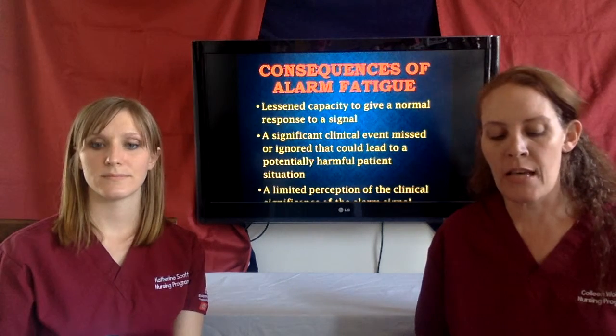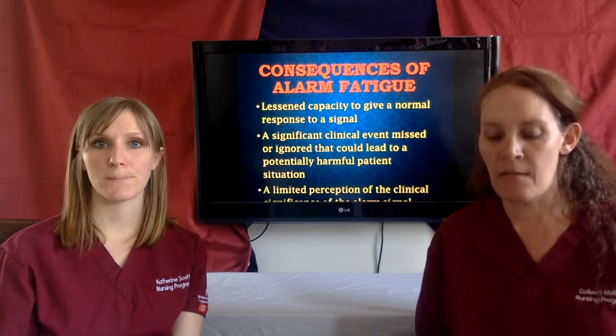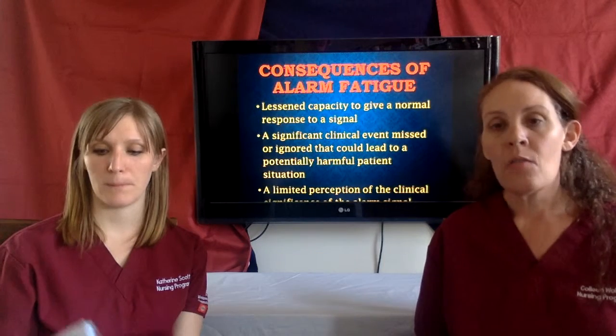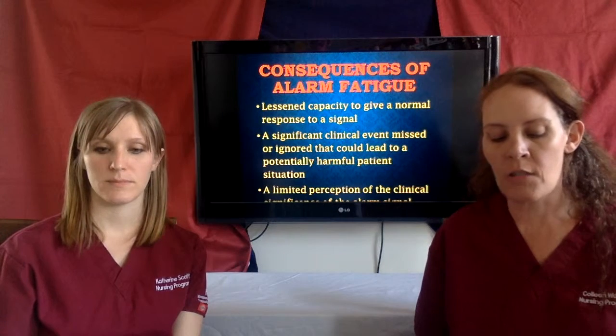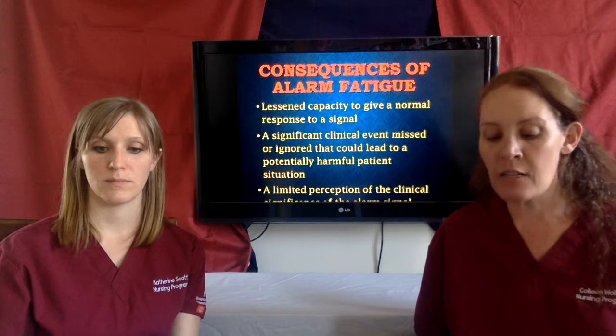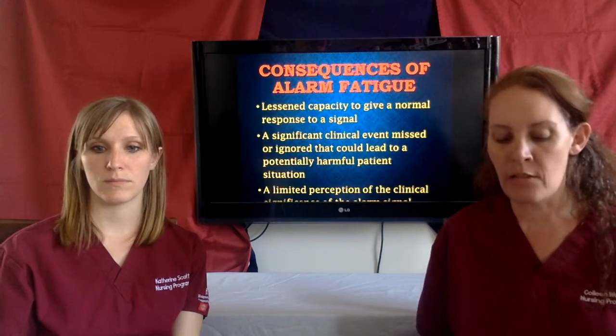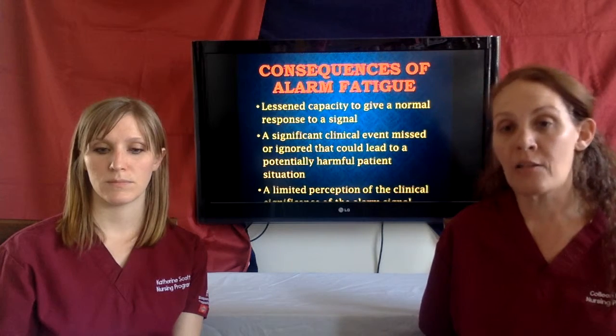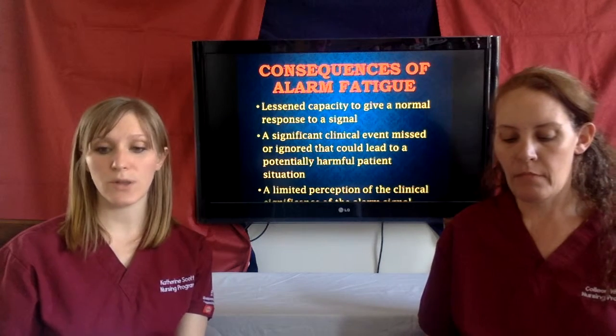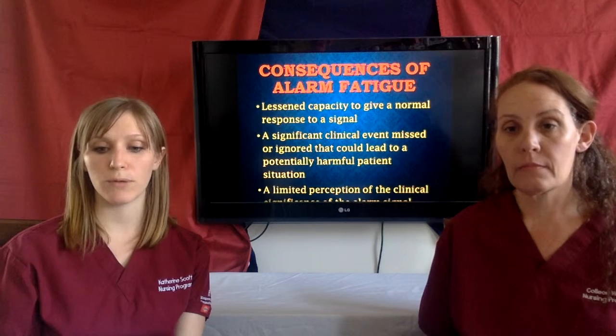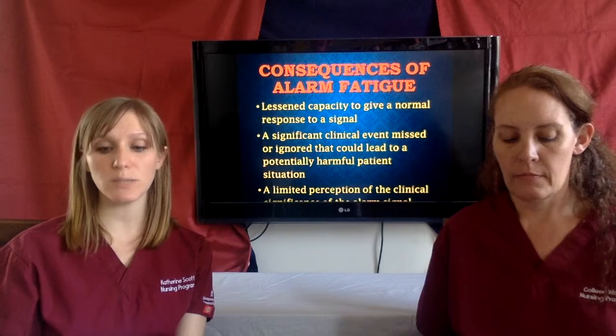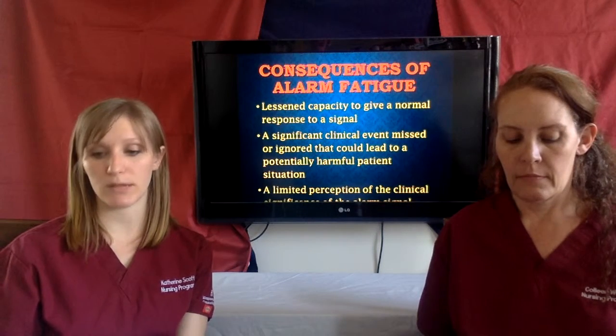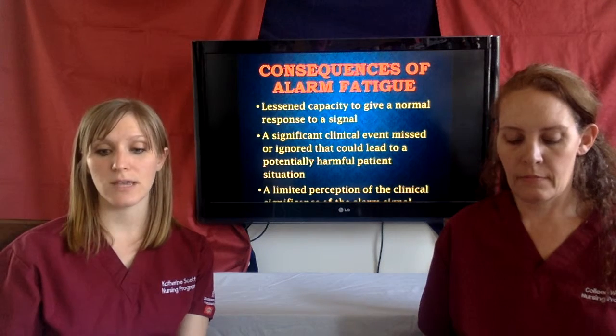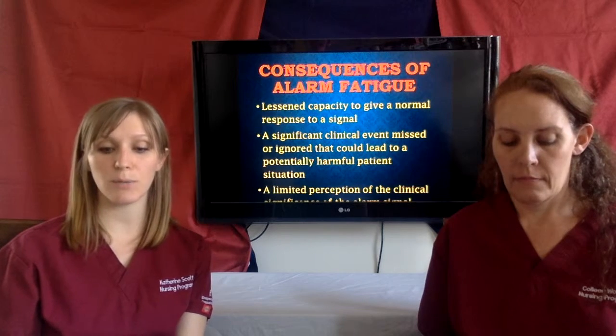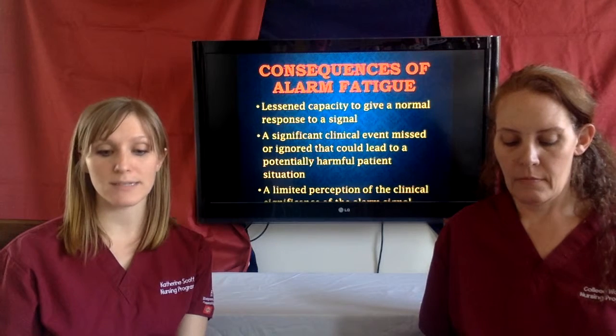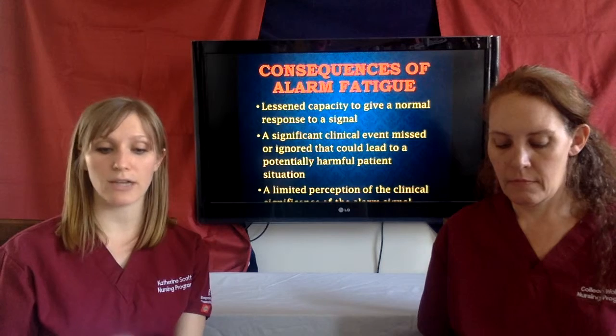Of these alarms, the Joint Commission estimates that between 85 to 99% of them do not require intervention by the nurse. We have found that evidence-based practice attributes these types of false alarms to parameter settings, not adjusting the alarms to the specific patient, improper sensor positioning, and improper skin preparation prior to the sensor application. These types of false alarms create a situation like the story of the boy who cried wolf. With so many false alarms going off, the nurse will eventually become desensitized to the alarms and not respond appropriately. This can result in missed or delayed reactions. If an alarm is false, this type of reaction isn't pertinent to patient safety. But if this alarm is signaling a decline in patient health, a missed or delayed reaction could cause the patient harm.